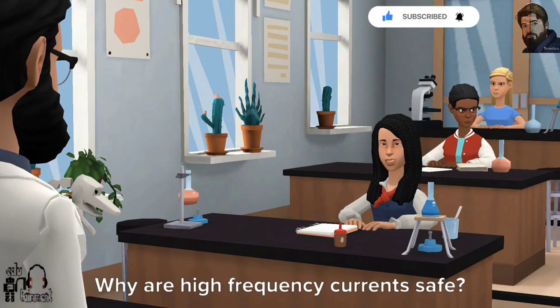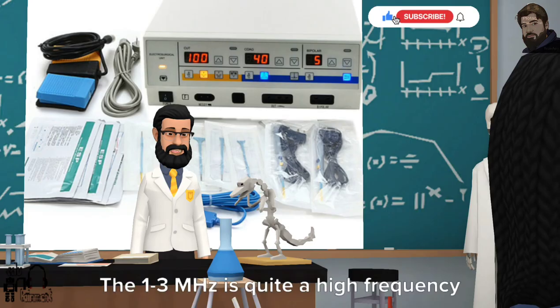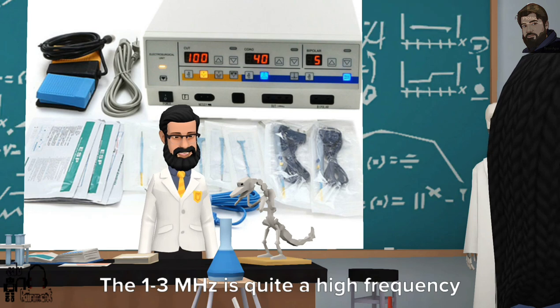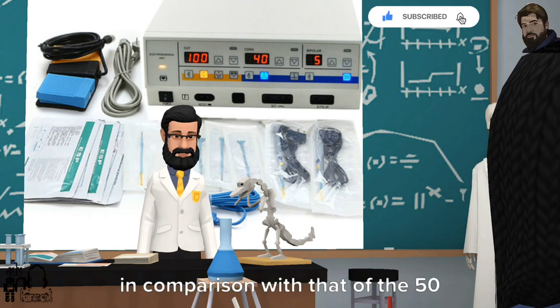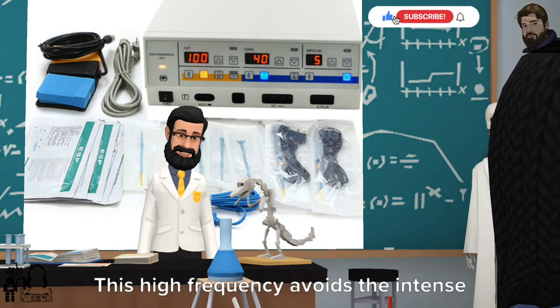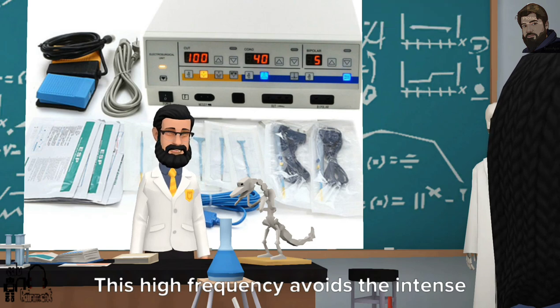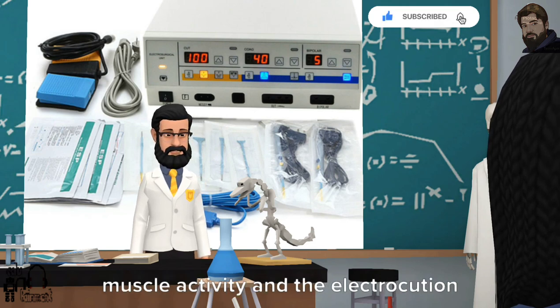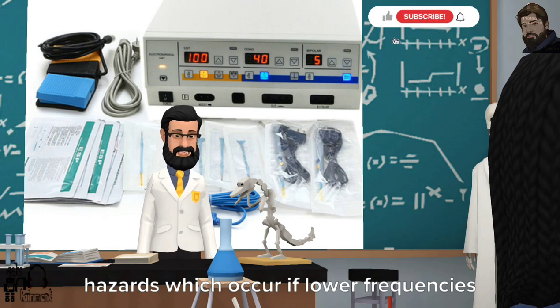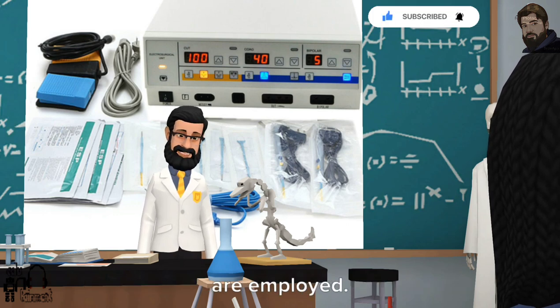Why are high frequency currents safe? The 1-3 MHz is quite a high frequency in comparison with that of the 50 Hz main supply. This high frequency avoids the intense muscle activity and the electrocution hazards which occur if lower frequencies are employed.